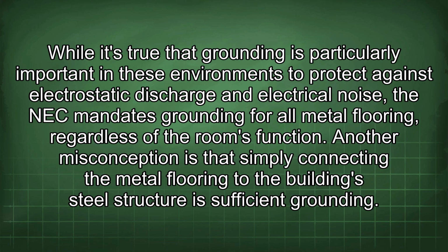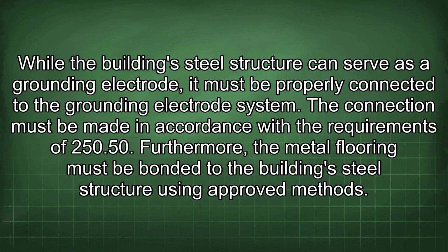Another misconception is that simply connecting the metal flooring to the building's steel structure is sufficient grounding. While the building's steel structure can serve as a grounding electrode, it must be properly connected to the grounding electrode system. The connection must be made in accordance with the requirements of 250.50. Furthermore, the metal flooring must be bonded to the building's steel structure using approved methods.